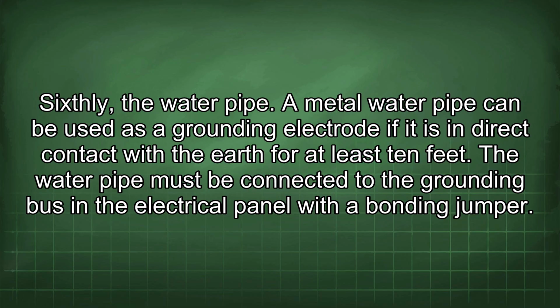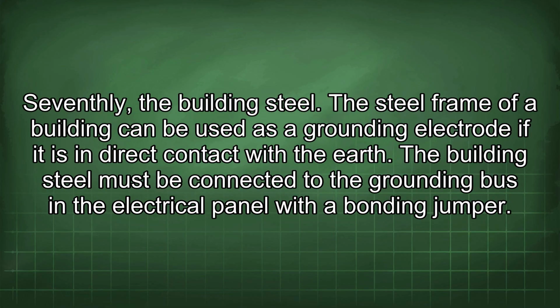A metal water pipe can be used as a grounding electrode if it is in direct contact with the earth for at least 10 feet. The water pipe must be connected to the grounding bus in the electrical panel with a bonding jumper. Seventhly, the building steel. The steel frame of a building can be used as a grounding electrode if it is in direct contact with the earth. The building steel must be connected to the grounding bus in the electrical panel with a bonding jumper.